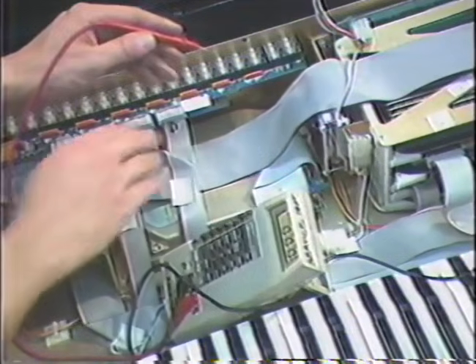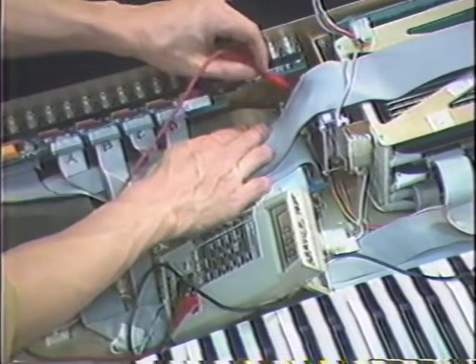If the E3 won't boot up on the internal hard disk, searches SCSI continuously, or displays a SCSI hardware error, first try and boot from the floppy disk. If you can, try and access the hard disk. If you can access the hard disk, erase the software from the hard disk. Copy software from the floppy to the hard disk. The software may be corrupted on the hard disk. If you do not have the customer system disk, the E3 will need to be recalibrated and retrimmed. If you cannot access the hard disk, check the power at the hard disk. It should be no less than 4.7 volts.